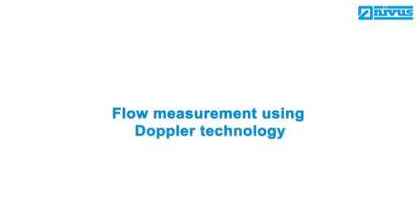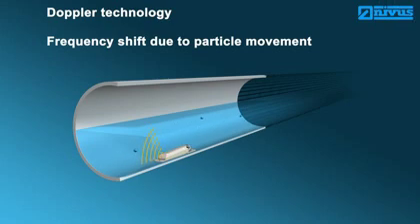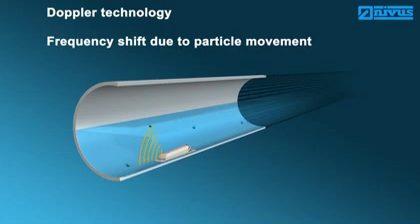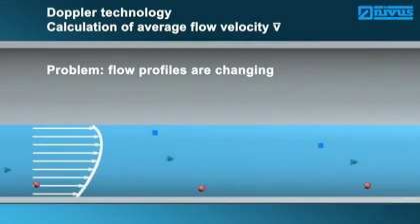Flow measurement using Doppler systems. The Doppler technology uses a sensor continuously transmitting ultrasonic signals at a constant frequency. The particles contained in the medium reflect the signal. The particle movement shifts the frequency of the reflected signal. The frequency shift is detected by the sensor. The greater the particle velocity, the greater the frequency shift. Doppler measurement is a spot velocity measurement — the sensor is not able to determine at which level the velocity has been detected.